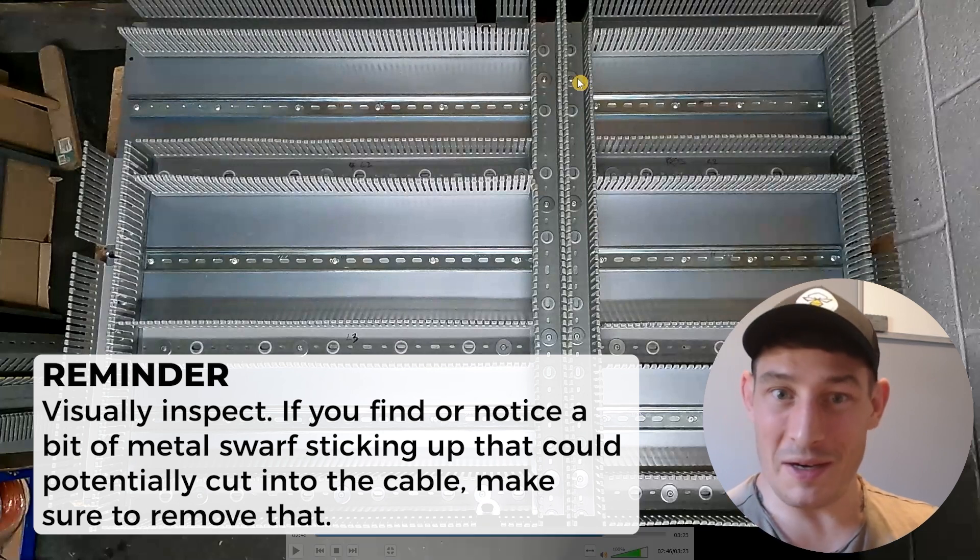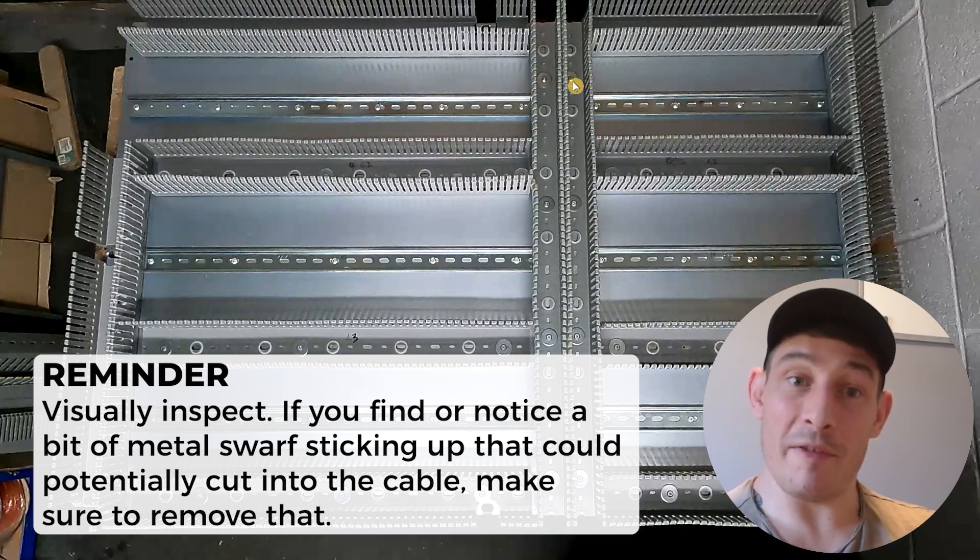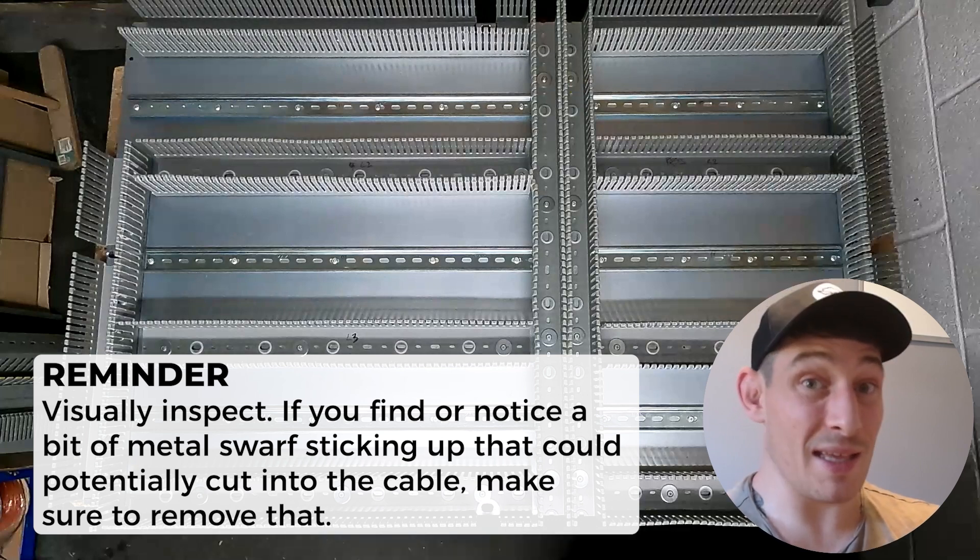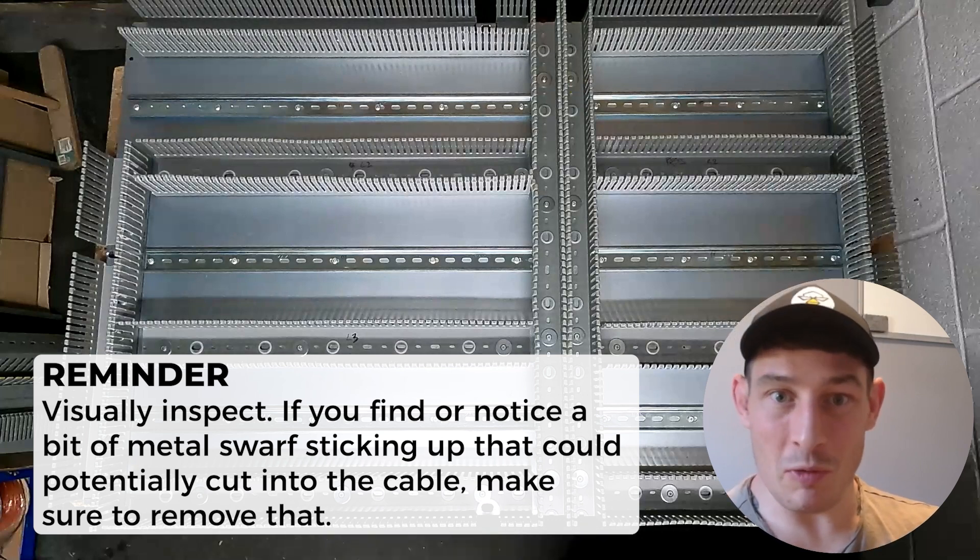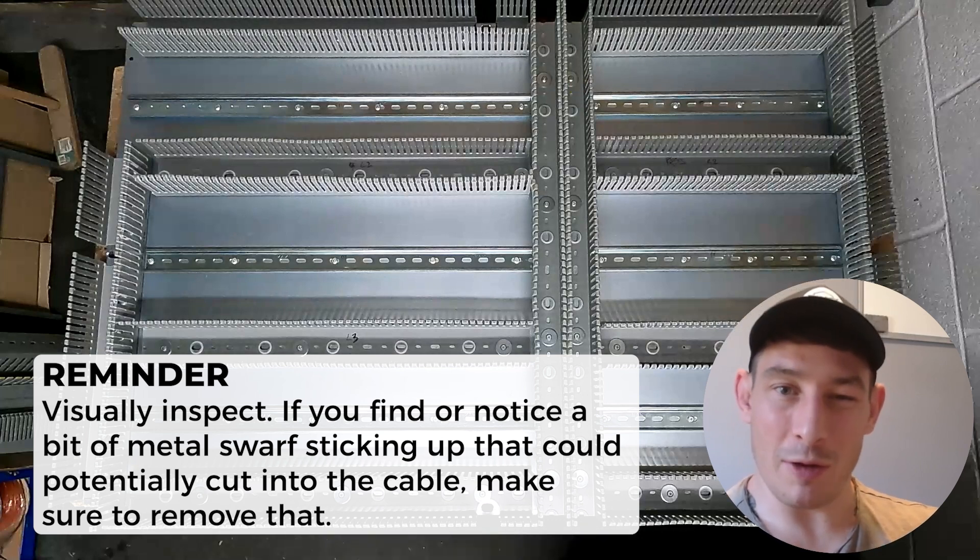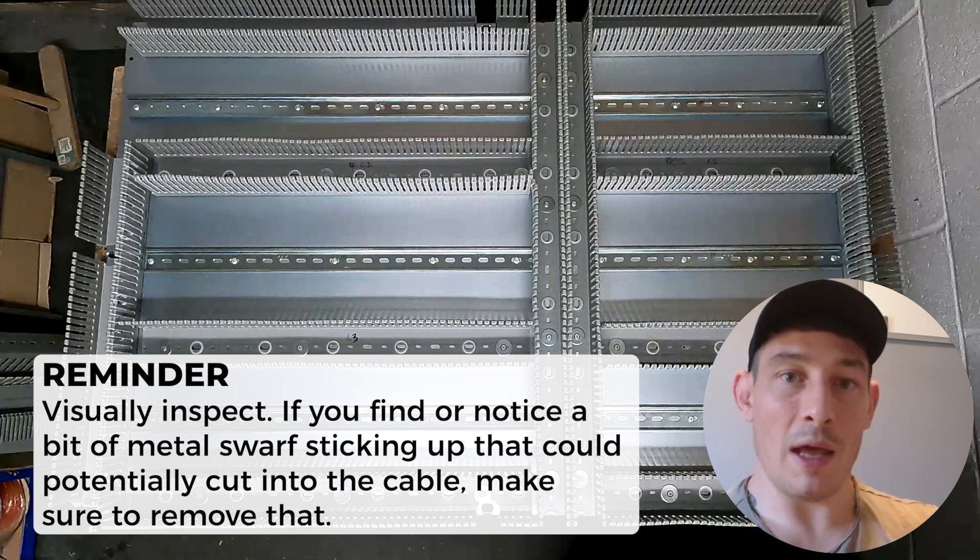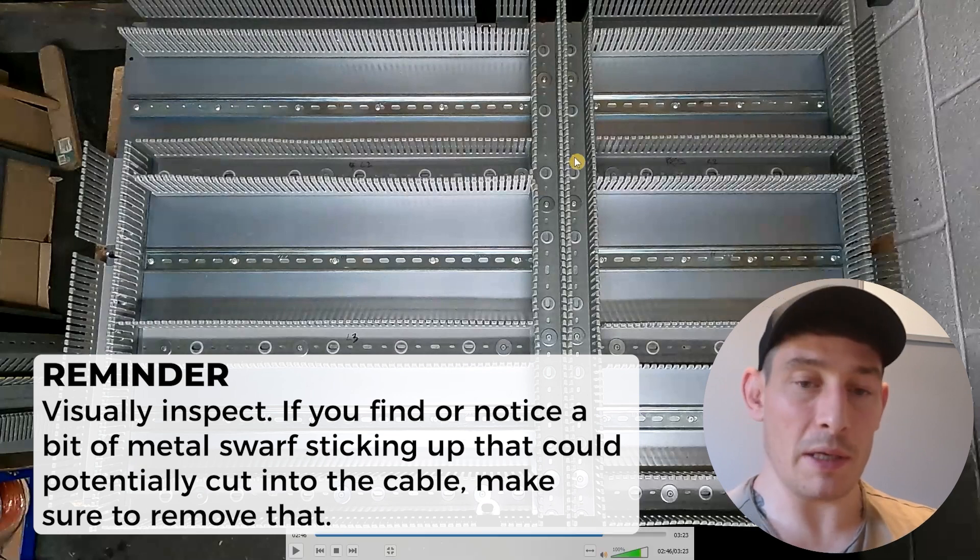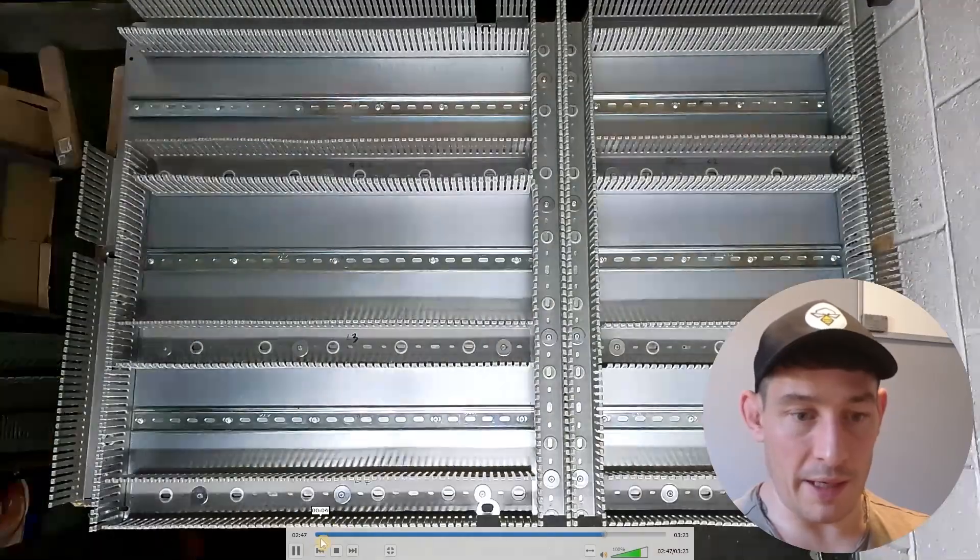Also another thing to point out and I've found this quite a few times is I would just visually inspect or run your finger, maybe not run your finger over because what I'm about to say. If you find or notice a bit of metal swarf sticking up that could potentially cut into the cable, make sure you obviously remove that. So you might have to loosen the tech screw, pull it out with some pliers and then just tighten it up again. So quick vacuum, get all of that cleared out.